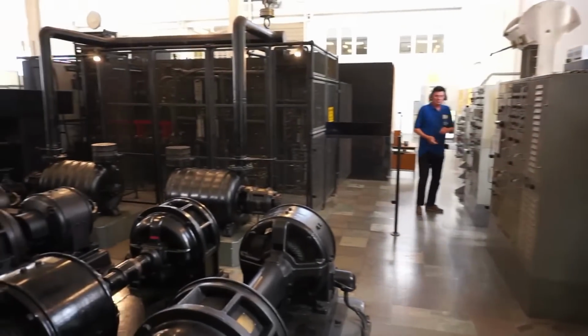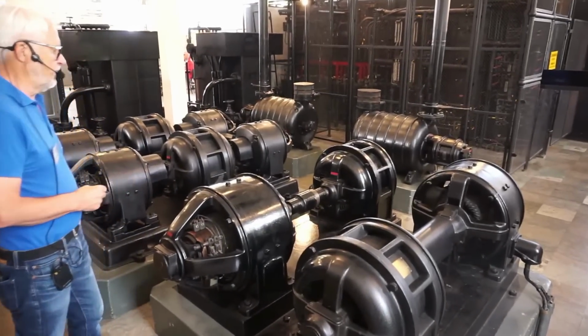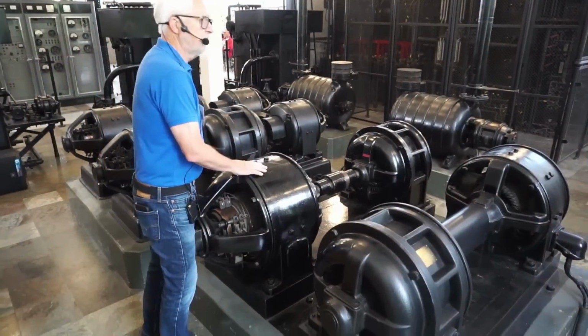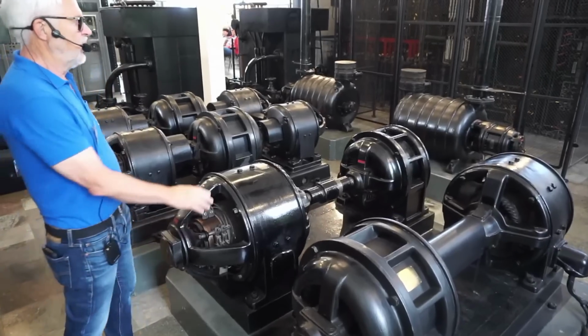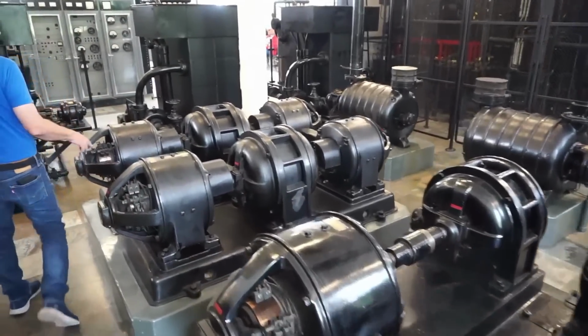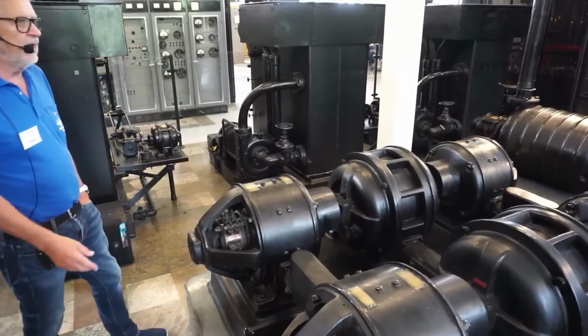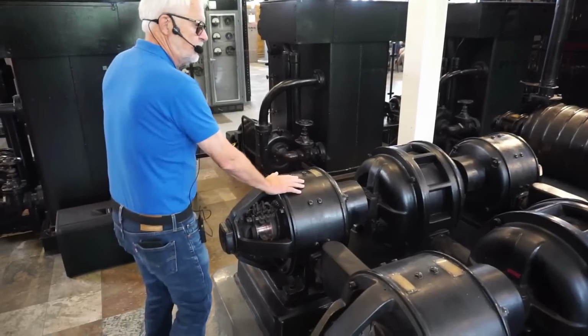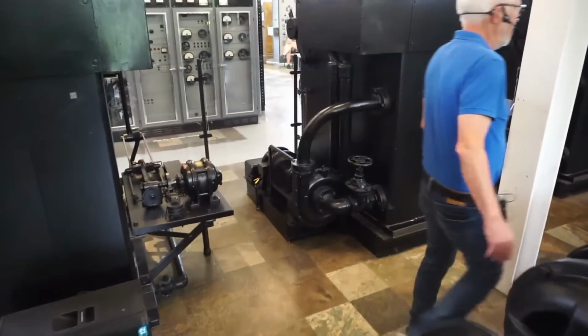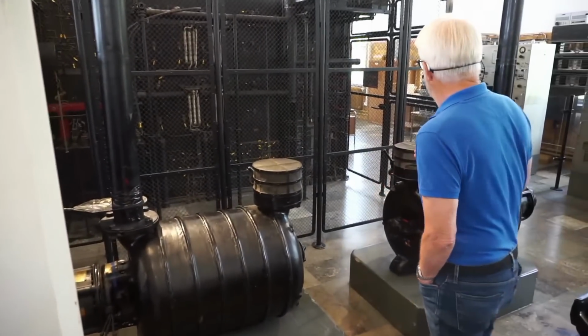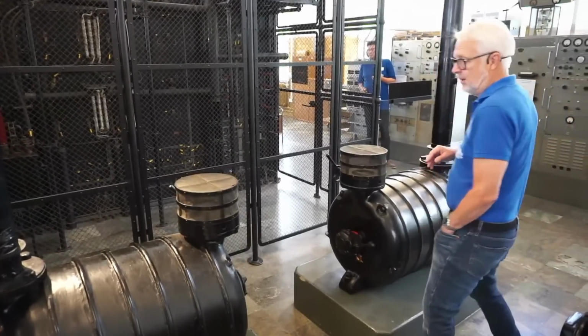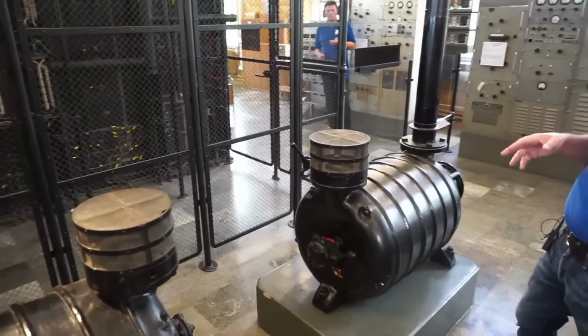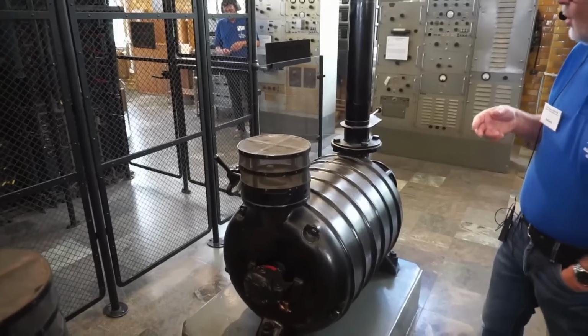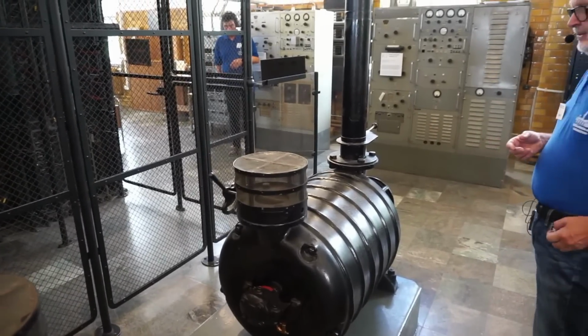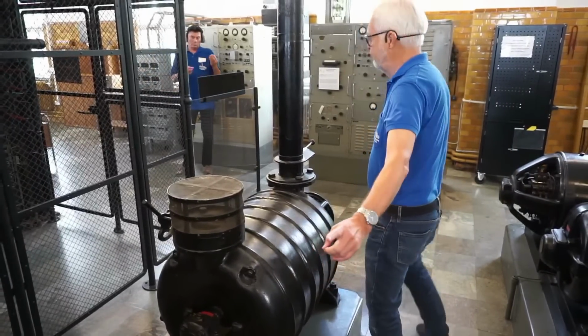Now, in front of me, we have a set of rectifiers that will give 500 volt DC. It is the current needed for the transductors. One is used, one is a backup. Here we have another set of transformers that gives 125 and 250 volt DC. This is used, and that is a backup. When we are controlling the motor speed, there will be a lot of heat on our contactors in the relay corridor. Here we have two cooling fans that gives compressed air to blow out electrical arcs and cool the contactors. We will use fan number 2 today, and the other is backup.